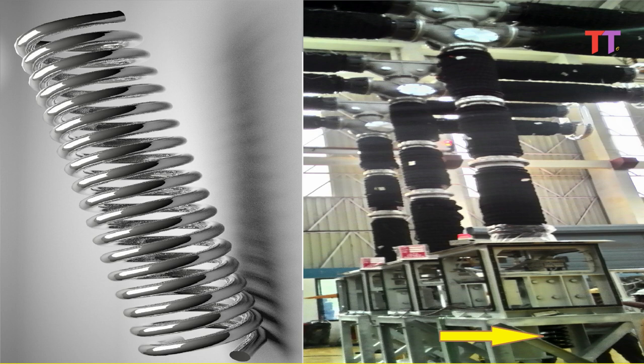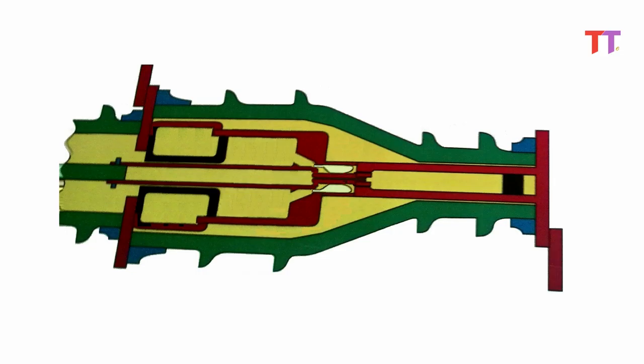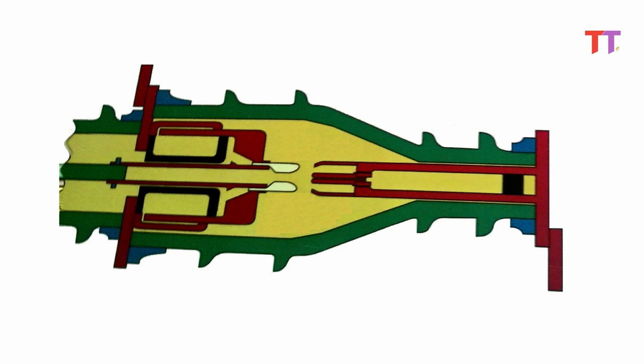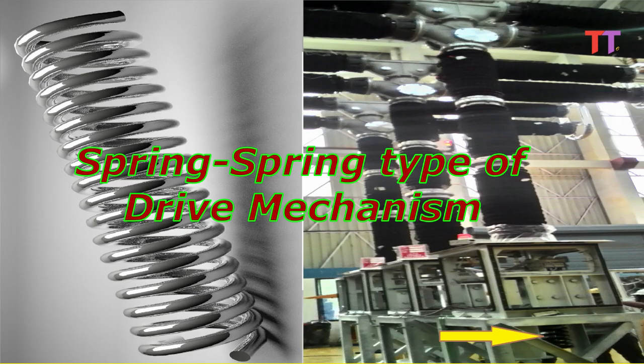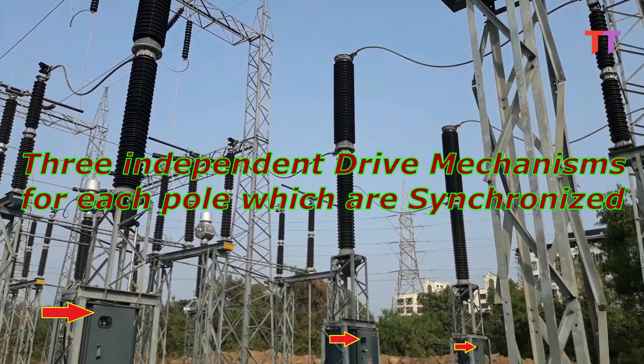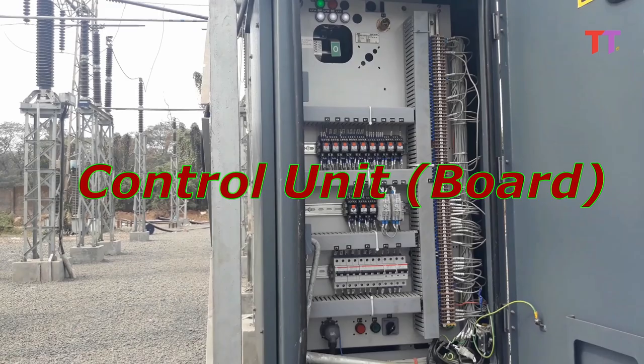Here we will see spring type drive mechanism, since in this drive mechanism both closing and tripping operation is done with the help of springs, hence called as spring type of drive mechanism. This is also called as pole operated circuit breaker, because there are three independent drive mechanisms for each pole which are synchronized, and there is a common control unit for all three.